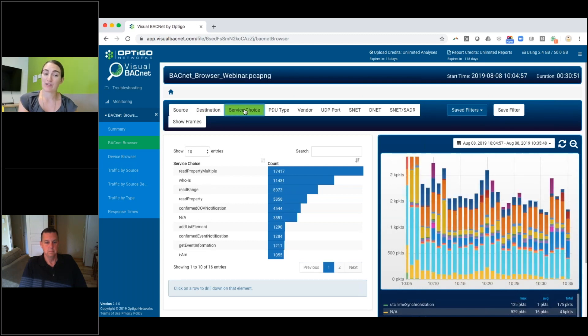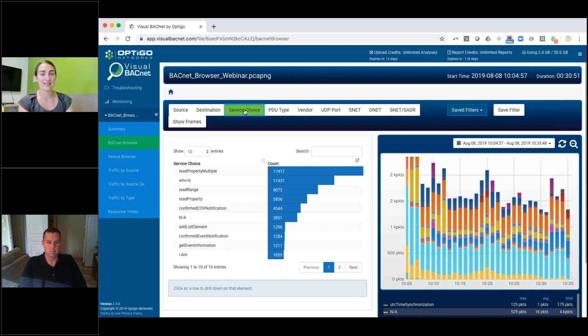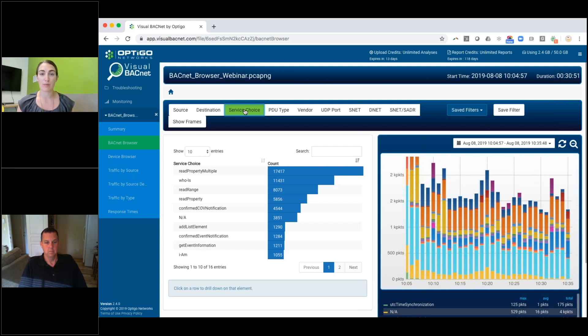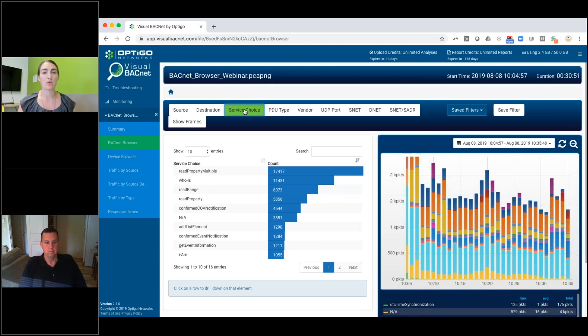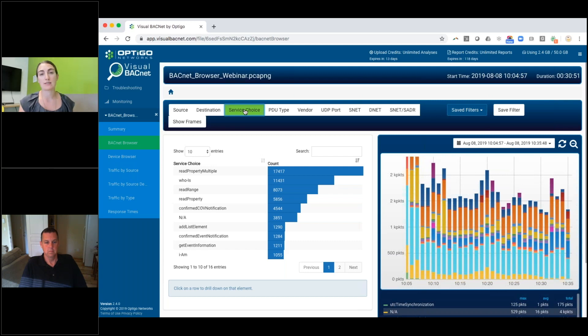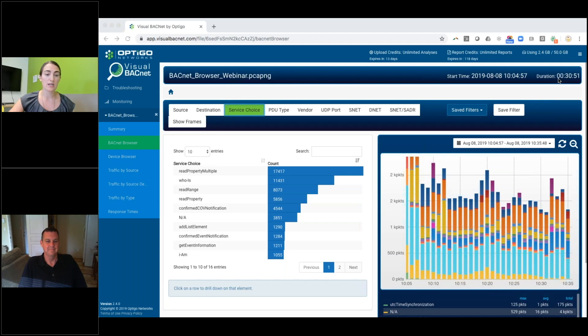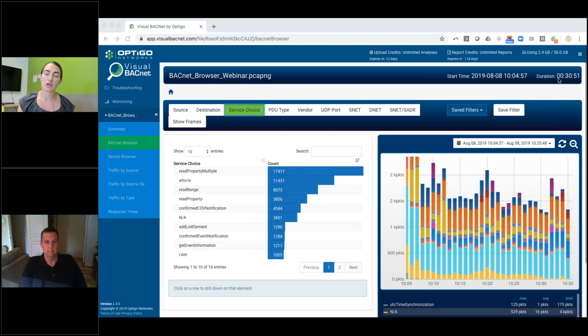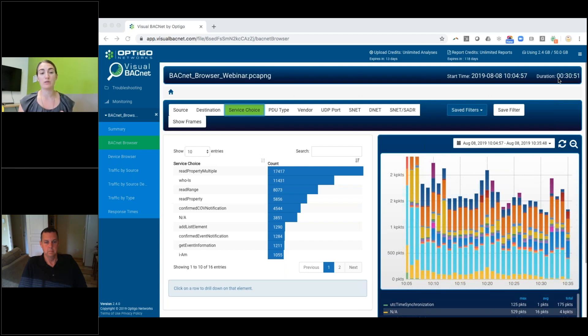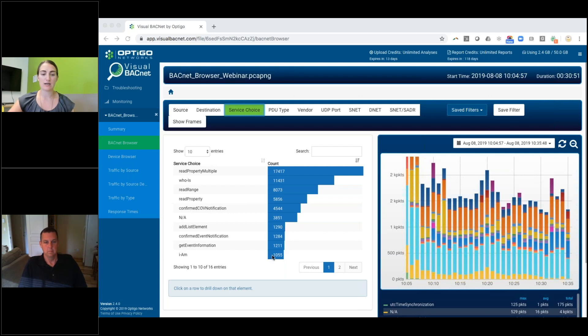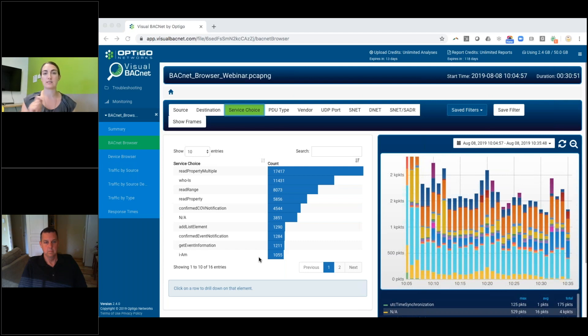One of my personal favorites is the service choice. This is telling you what types of traffic are most common on your site. In this example, we've got a lot of read property multiples. That tends to make a lot of sense. You're looking for a lot of data, especially if you're pulling analytics or just generally trying to send the data from one controller to another. You're going to be asking to read the property. The second one in this one is who is. That means there's 11,000 packets in this half hour capture that are saying who is this device. And they're looking for devices. That could be a little problematic. If they're global who is, we have a diagnostic check for that. But based on the fact that there's only 1,000 I-Ams, it's likely that these are specific who is. Who is device 73? Who is device 1084?